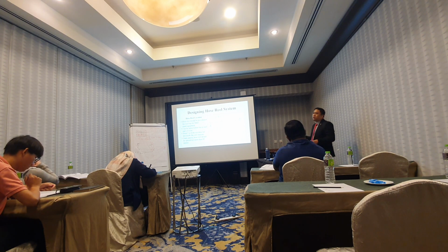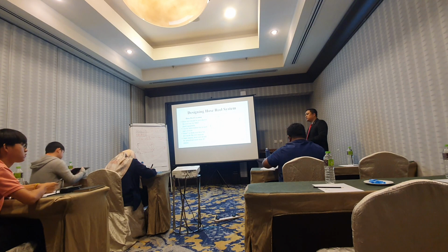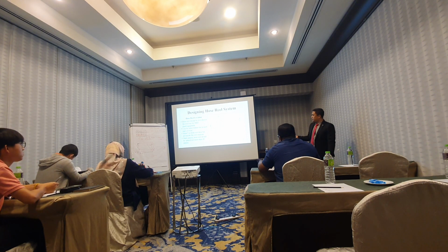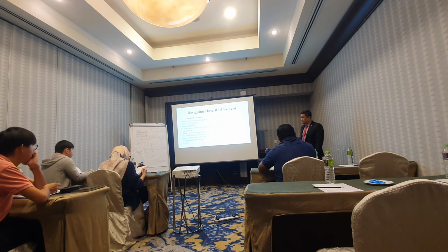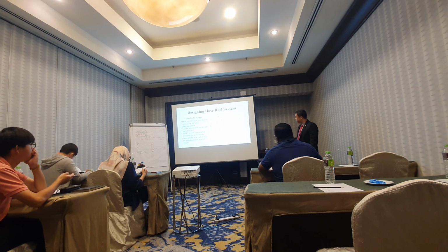And for this new requirement, I've attached in the notes at the back yang surat yang telah dikeluarkan oleh pihak bomba about this arrangement lah. Yang mana they allow for this arrangement. Kalau dulu we need to have 30 meter, this hose reel to this hose reel, it must be located at not more than 30 meter. Now they are allowing for 48 meter for open spaces lah.